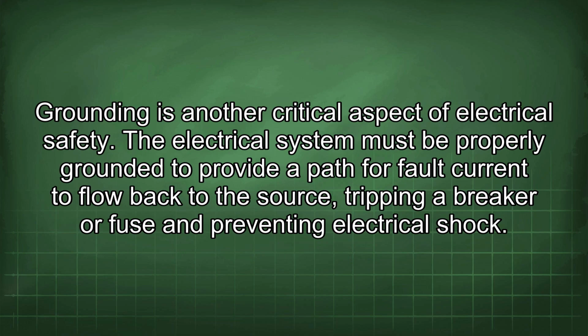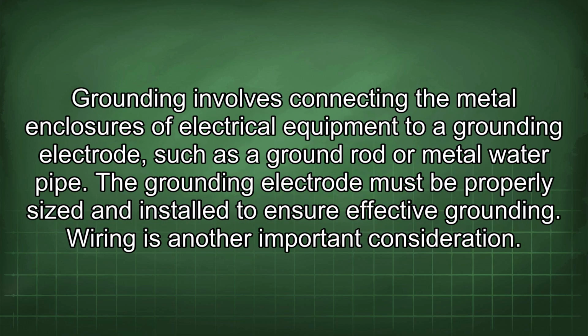Grounding is another critical aspect of electrical safety. The electrical system must be properly grounded to provide a path for fault current to flow back to the source, tripping a breaker or fuse and preventing electrical shock. Grounding involves connecting the metal enclosures of electrical equipment to a grounding electrode, such as a ground rod or metal water pipe. The grounding electrode must be properly sized and installed to ensure effective grounding.